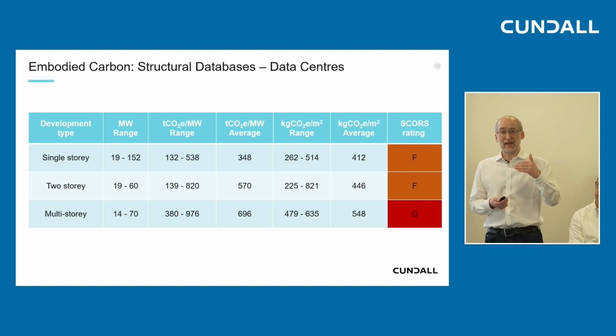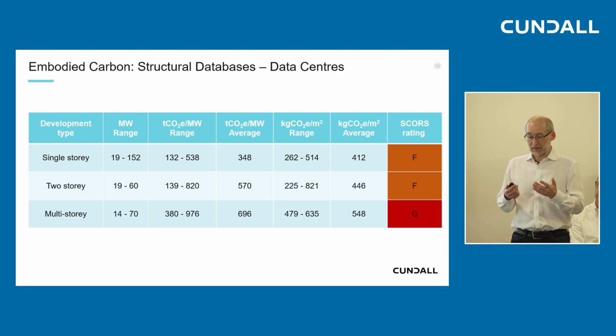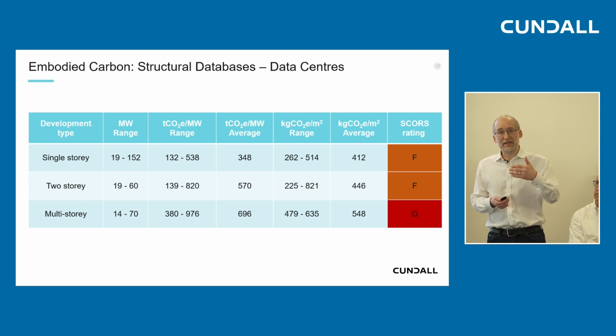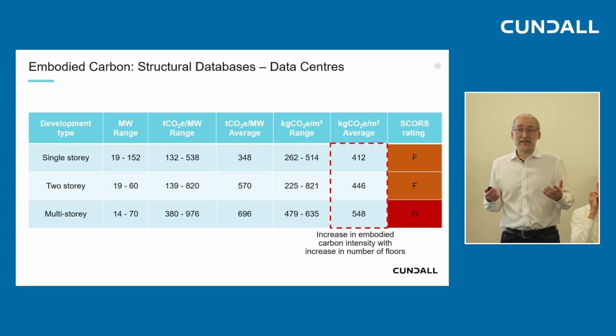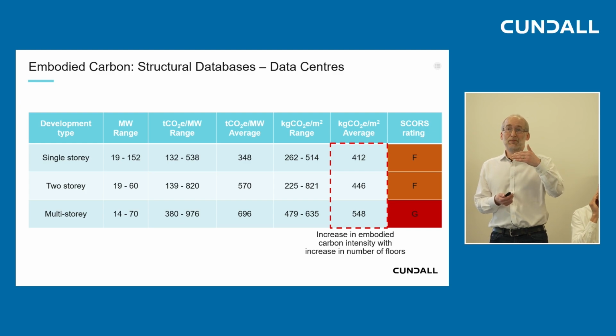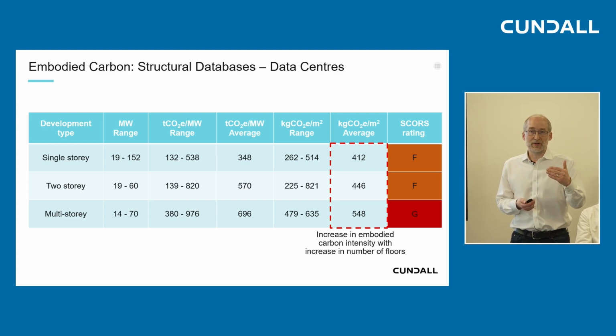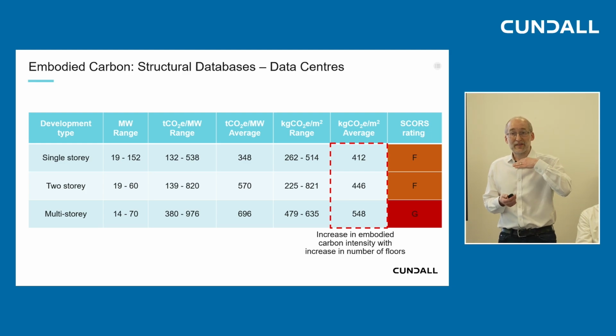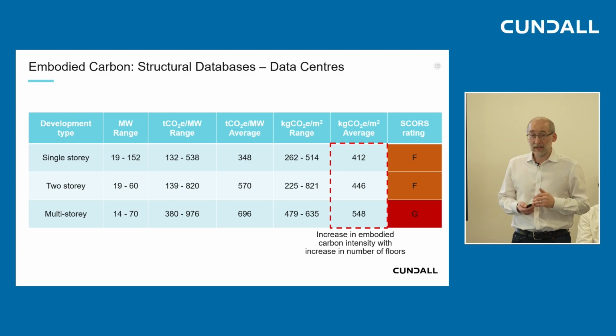And we've categorised it in a few different areas. So we've looked at single-storey, two-storey, multi-storey. We've had a look to see whether or not there's a relationship between the embodied carbon in each development and the megawatt of IT capacity, but also looked at it in terms of the embodied carbon intensity per square metre of GIA. In terms of the structures, we haven't really seen much of a correlation between the embodied carbon and the IT capacity, but what we have found is there's a strong correlation with the increased number of stories that you add onto a building will increase the embodied carbon intensity, which makes sense because data halls have quite heavy equipment. They tend to have long-span structures, so we have to put some heavy structures in. So you expect that kind of increase in intensity as you go up the building.